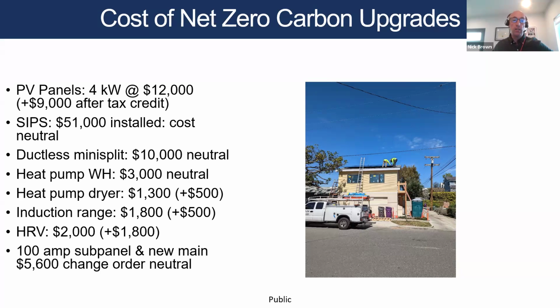And they required me to put in this dual meter panel, one for the main house, one for the ADU. The ADU has a 100 amp sub panel and the main house has a 125 amp panel. Both are all electric with that size panel. So don't let someone tell you you've got to have 200 amps or even 400 amps to electrify a building with solar.